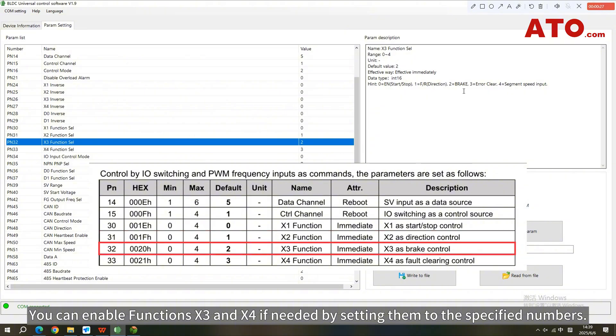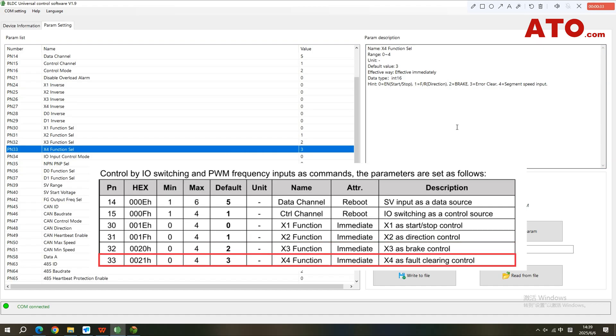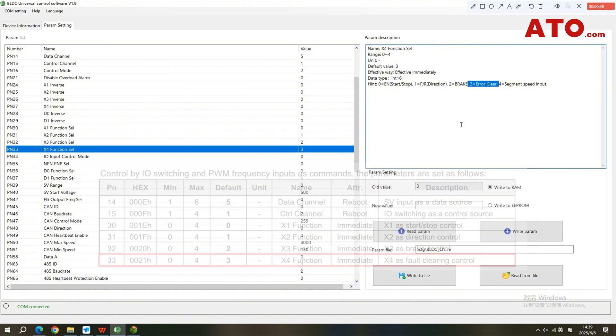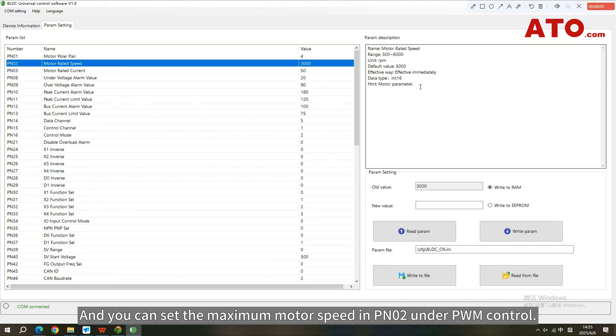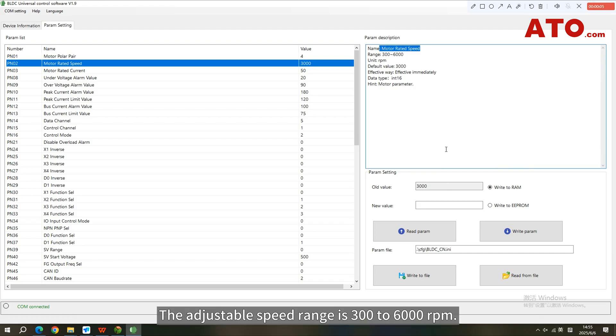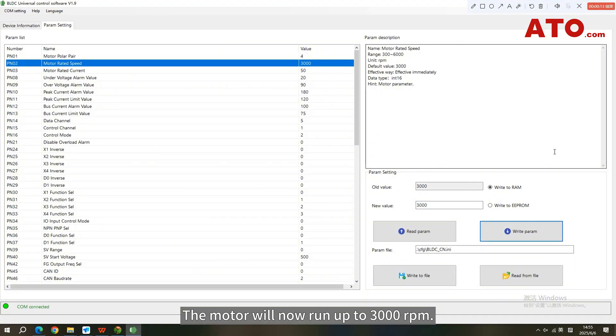You can enable functions X3 and X4 if needed by setting them to the specified numbers. You can also set the maximum motor speed in PN02 under PWM control — the adjustable speed range is 300 to 6,000 RPM. For example, enter 3000 in the New Value field and click 'Write Parameter.' The motor will now run up to 3,000 RPM.